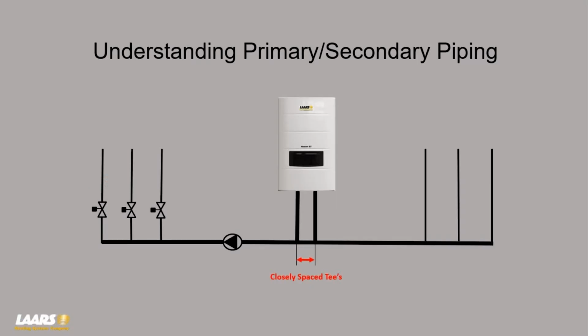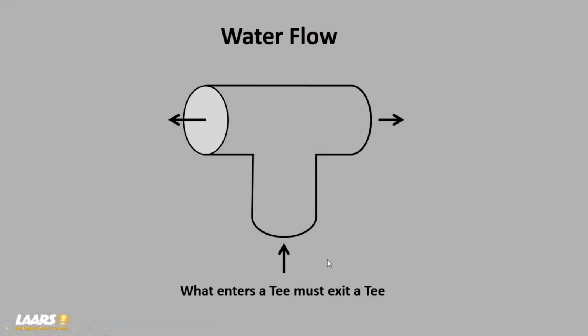Next, I want to talk about is primary, secondary piping. This is just basic that I'm going to go through for you. Primary, secondary piping is 2 closely spaced T's. Okay. What enters a T must exit a T. So if I'm putting 12 GPM into a T, somehow 12's leaving. Either 6 and 6, or 4 out one side, 8 out the other, or maybe all 12's coming out one side.